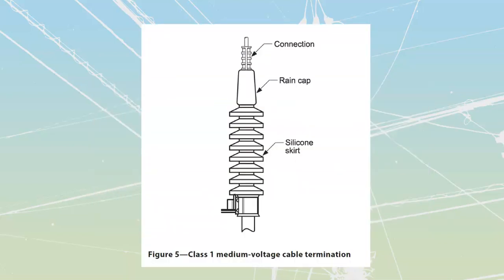Our next termination is Class 2. It's stress relief and anti-tracking, so it has a bunch of skirting on it, generally preventing tracking from going across from one to the other. The most common ones are silicone and porcelain. You're going to see silicone, porcelain, and glass used for all of these because they are vitreous or glass-like on the surface.